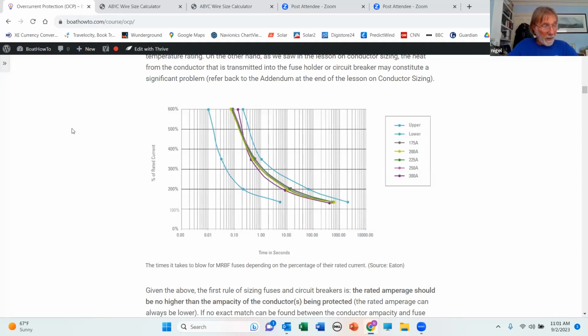so that you've got that high AIC rating. All of these fuse holders have stainless steel bolts and nuts and washers. Stainless steel has less than 10% conductivity of copper. So if when we put these fuses in, we bolt down and we accidentally get a stainless steel washer between the fuse and the conductor terminal. So now this fuse holder was laying flat in the bottom of the boat. We loosened the nuts. These ANL fuses have a slot on one end, and you push it in like that, and then a slot in the other direction this way, and you push it in and slide it in, and then you tighten the nuts.